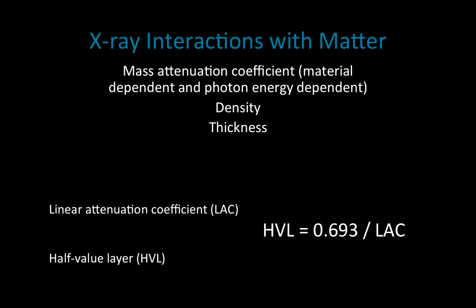The half value layer really depends on the atomic number of the material — and that makes sense for lead. It also depends on the density of the material and the energy of the x-rays that we're trying to stop.